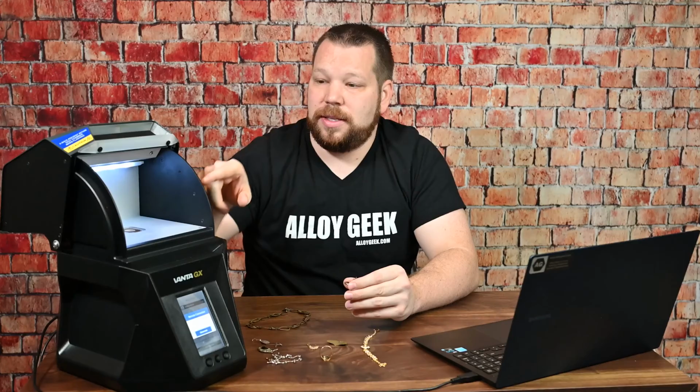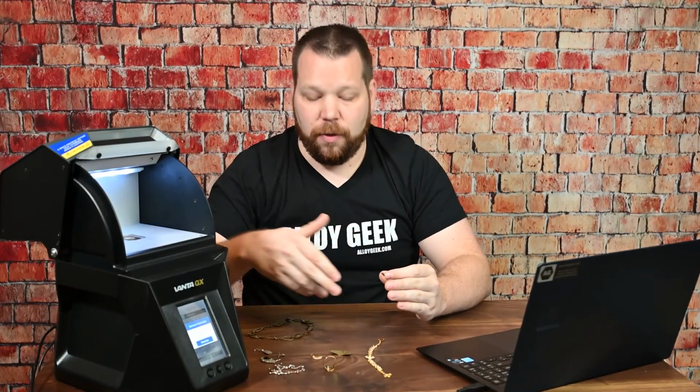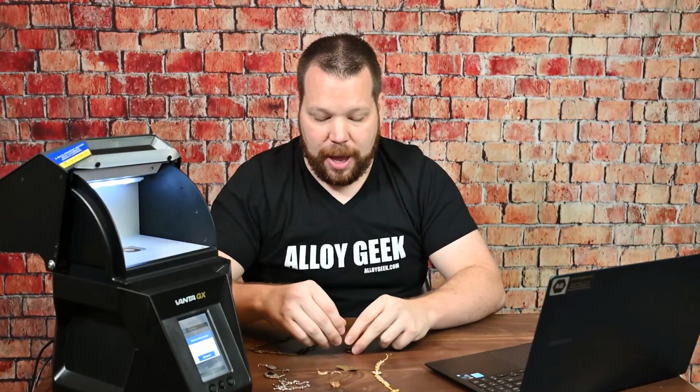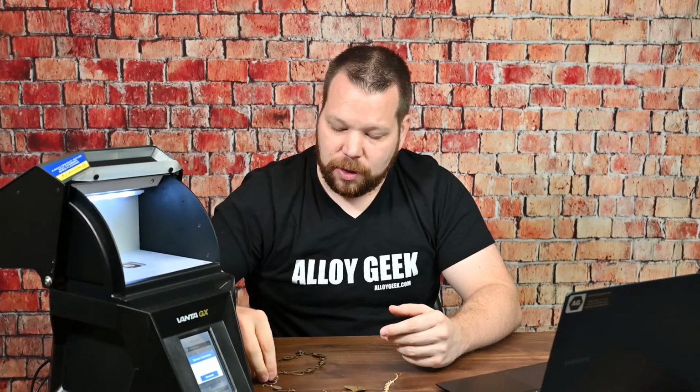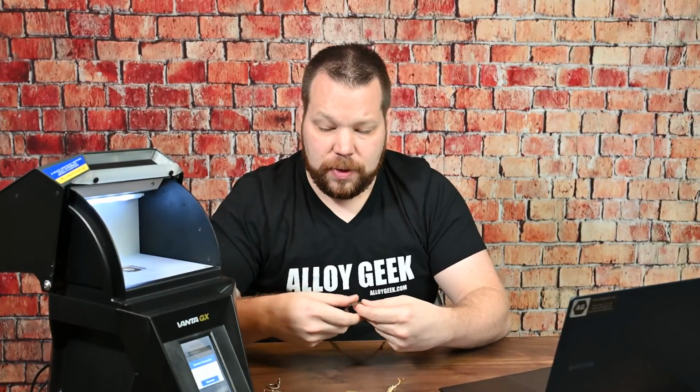Now, all the air gap you see around the band there doesn't matter so much for an analyzer like this. The Benchtop XRFs, what they do is the sample chamber here, all this extra room, dissipates the X-rays from coming back in, versus if you were to test this with a handheld directly on a table surface and you were able to get some of the table x-rays and interference coming back. So it actually gives you a really clean result. I recommend if you're doing jewelry or small pieces like this, like weld wire or jewelry, that you would use a Benchtop XRF.